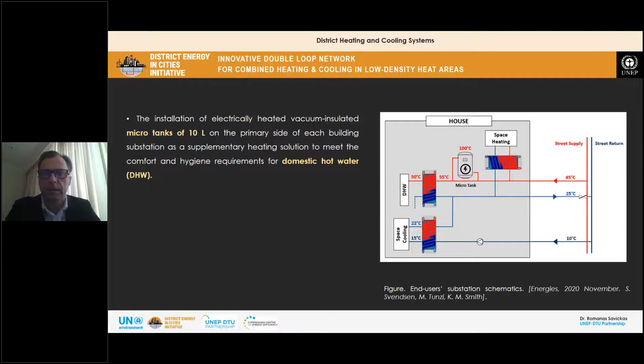For the house installations, the installation of electrically heated insulated micro tanks of about 10 liters each on the primary side of each building substation as a supplementary heating solution. So to meet the comfort and hygiene requirements for domestic hot water, I've seen questions about Legionella, so for our participants and presenters, this will solve all problems and issues related with Legionella. As you see, from the supply network you can receive 45 degrees, so you increase temperature, and also with this 10 liter micro tank, you can boost temperature and solve these issues.